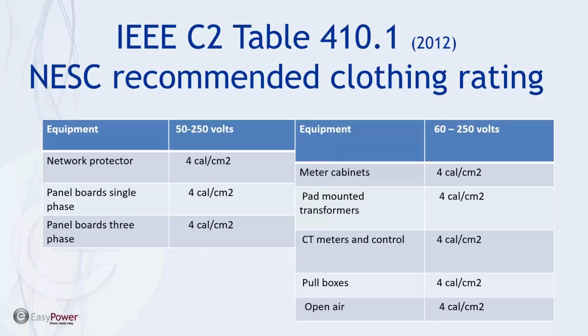Back in 2012, in the NESC standard released at the time, which is the National Electrical Safety Code, a study was referenced that had been conducted by two large utility companies where they surveyed all the equipment and categorized by calorie range the maximum calorie for that particular equipment and voltage. And in table 410.1 of the NESC 2012 version, they have this, and I've rearranged it because table 410.2 includes higher voltages and 410.3 includes very high voltages.